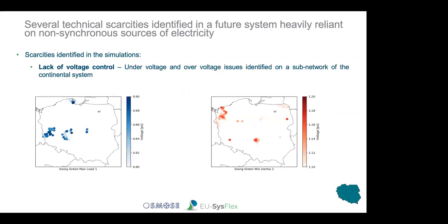On the next slide, PSE conducted analysis of the Polish network, a sub-network of the continental power system, and identified significant scarcities in reactive power, with both under and over voltage issues a concern due to increasing renewable generation, especially wind. What's interesting is that the actual non-synchronous renewable levels in Poland in our 2030 scenarios were quite low, yet we still saw significant issues in reactive power scarcities.